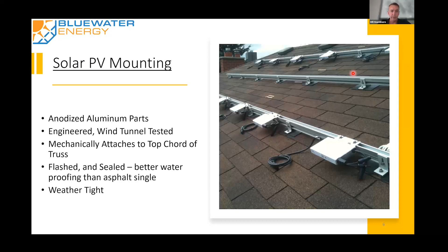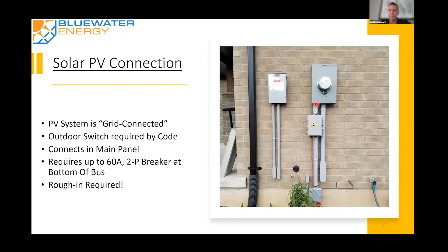So solar PV connection, I'm going to cover this in two slides. First, here's the hydro meter, everybody's familiar with that. I showed the inverter previously, and I'll show you how all the components tie together. Out of that inverter, we come to this disconnect switch, which is required by code and utility standards, so there's a means to shut the solar PV system down if ever required. Really the only time that's needed is if work is being done on the lines by the utility crew, and they want to make sure we're not feeding anything back onto the lines and energizing the distribution system while work is being done, so it can be done safely. This shows that there will be some visible signs of a PV system on your home, one of which is this switch, which has to be installed within one meter of the hydro meter.